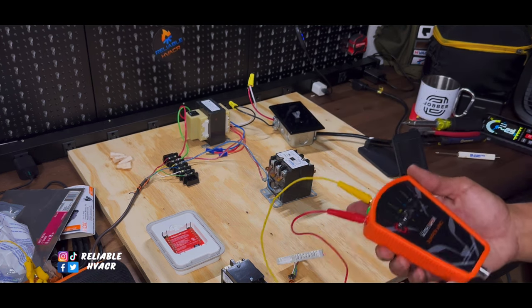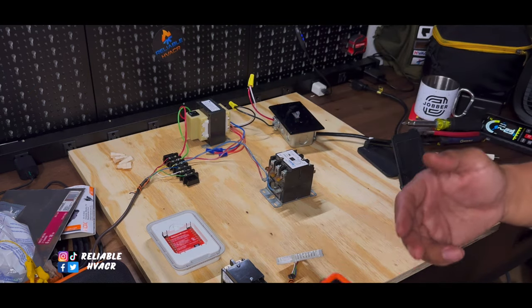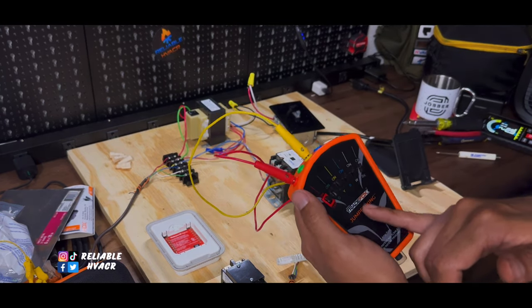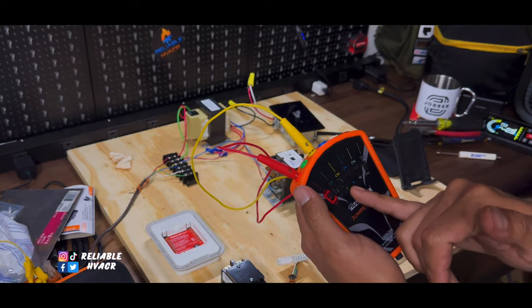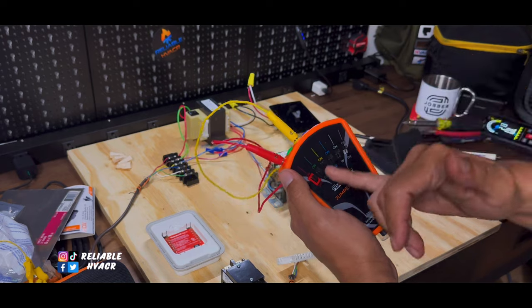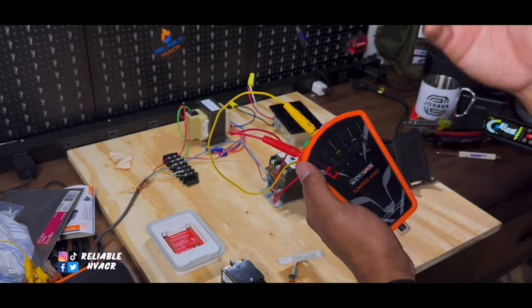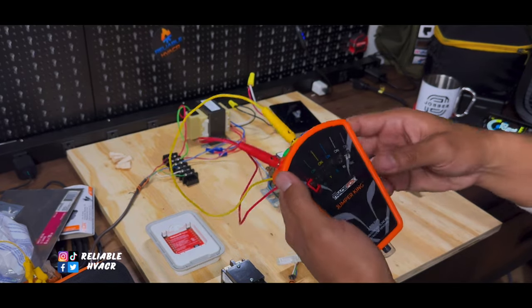But, if you're up there, and you're not sure what's causing an issue, you can go one by one. So, I would have been going to the blower motor first. That would probably be my first check, is a blower motor, because you can turn it on and off there. And then, once you start, you eliminate that. If it didn't trip on that, then you go to cooling, and it might be something with the compressor.